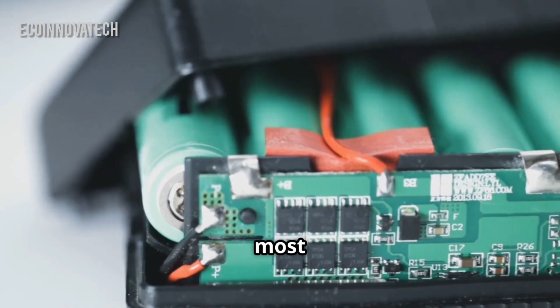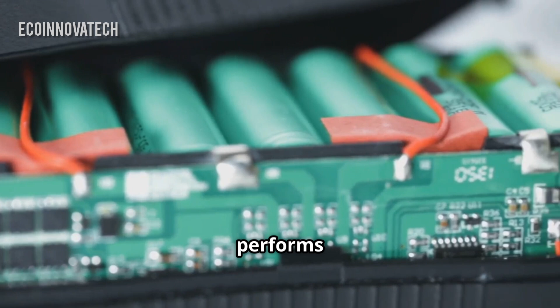At the most fundamental level is the Battery Management System, or BMS. This is the battery's guardian, a dedicated computer that monitors every single cell, tracking its voltage, temperature, and state of charge. The BMS ensures the battery operates within its safe limits, protecting it from overcharging or overheating. It performs cell balancing to maximize performance and lifespan, and in the event of a fault, it can instantly isolate a problematic module to prevent a cascading failure. The BMS is the foundation of battery safety.